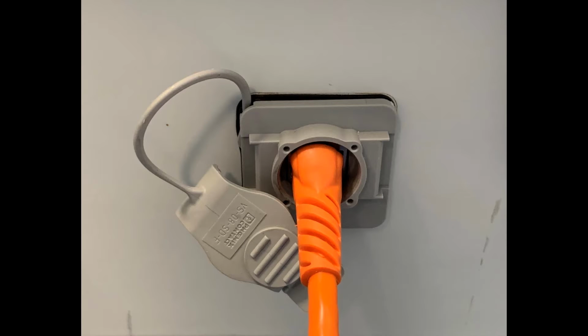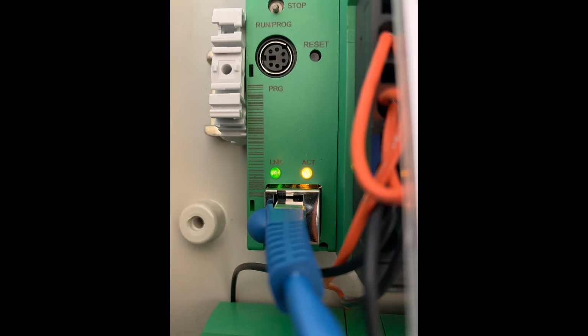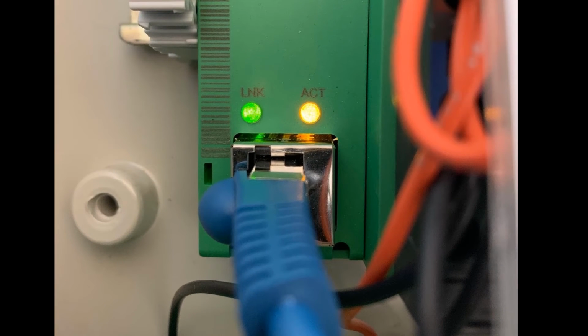Our short Ethernet cable goes to a pass-through connector that passes through the side of the plastic touch panel, and then an Ethernet cable will run from the touch panel to the dryer itself, and that will also enter into the dryer through another pass-through connector in the bottom of the power box. Inside the power box, there's another short blue or black Ethernet cable that goes from the pass-through connector up to the PLC itself. Here we can see the PLC Ethernet port and then link and act lights on there as well. Hopefully the link light is lit up and the act light is flashing.